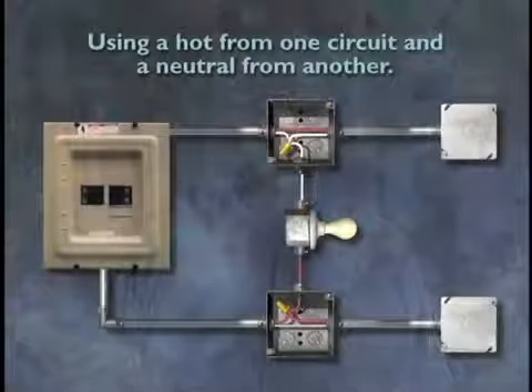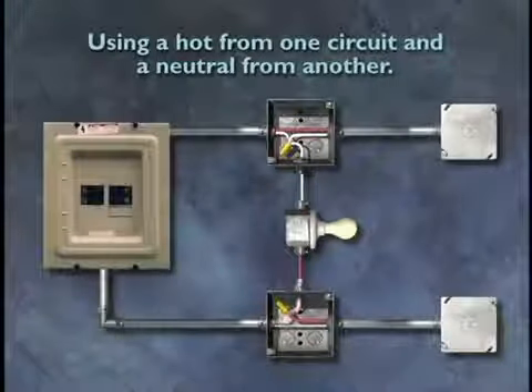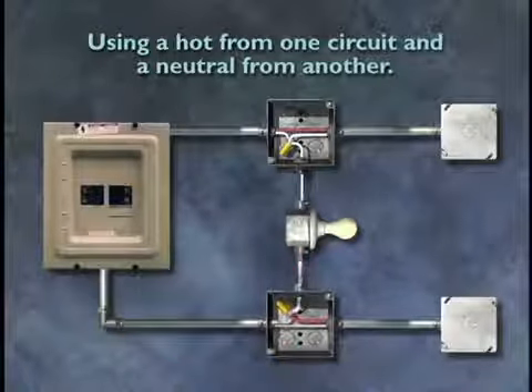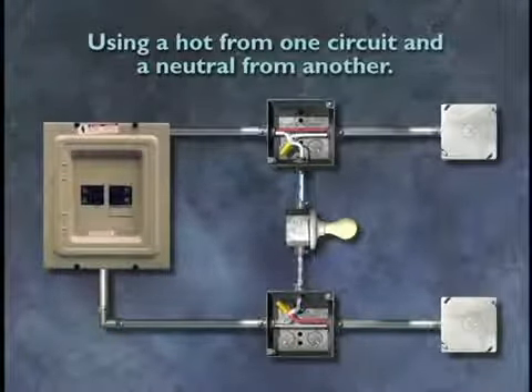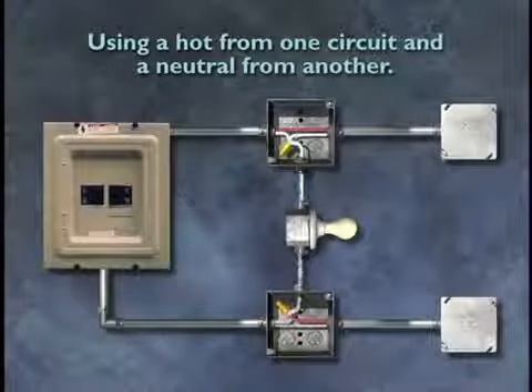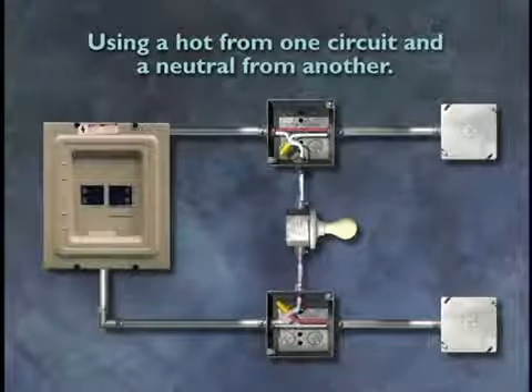So far, we've seen only one example of how to misconnect neutrals, but there are several other ways to go wrong. Here are some examples. In this example, the hot comes from one circuit and the neutral goes back on another. The net current equals the full load. Everyone knows not to do this, but we do see this error at times.